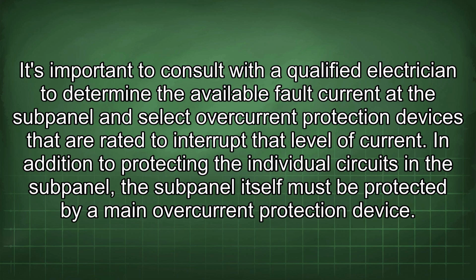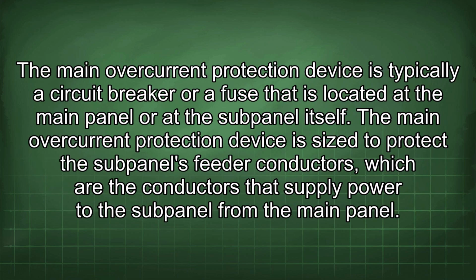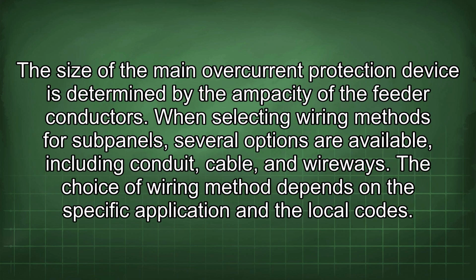In addition to protecting the individual circuits, the subpanel itself must be protected by a main overcurrent protection device. The main overcurrent protection device is typically a circuit breaker or a fuse that is located at the main panel or at the subpanel itself. The main overcurrent protection device is sized to protect the subpanel's feeder conductors, which are the conductors that supply power to the subpanel from the main panel. The size of the main overcurrent protection device is determined by the ampacity of the feeder conductors.